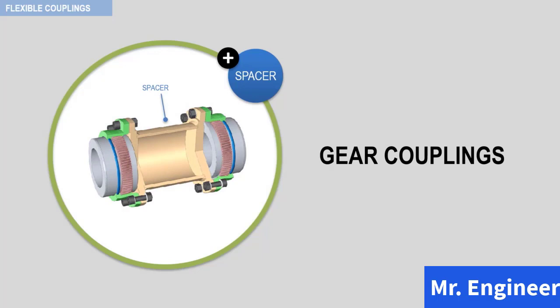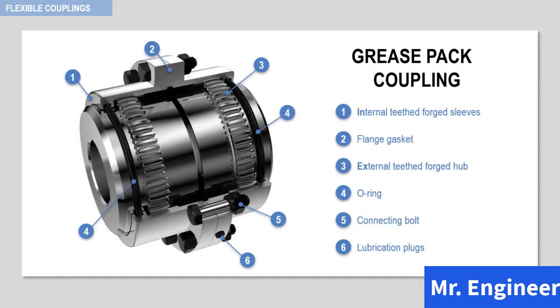Grease-packed couplings, like the one highlighted here, are normally designed with hub-mounted external gears, and the internal gears are part of a sleeve-type spacer which serves as a retainer for the grease lubrication. The flange joint of the sleeve is either precision ground to avoid lubrication leaks, or has a gasket between the two flange faces. The sleeve ends are fitted with O-ring seals, as depicted here, to keep dust out and lubrication in.